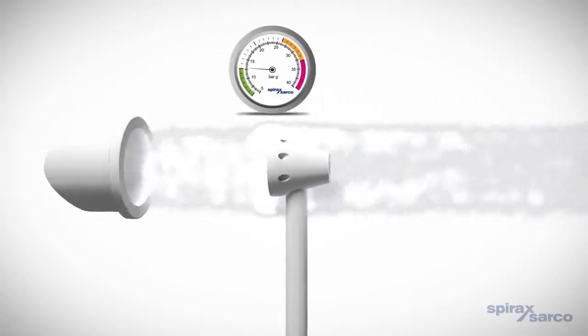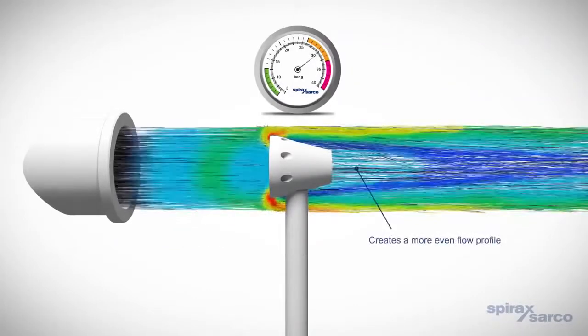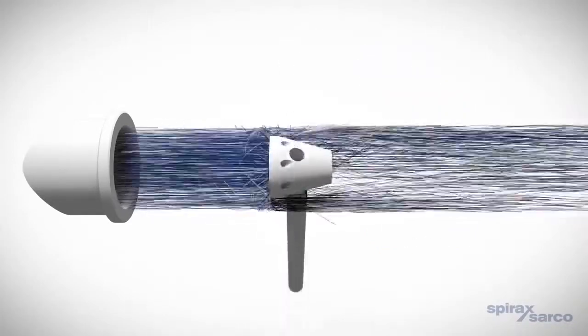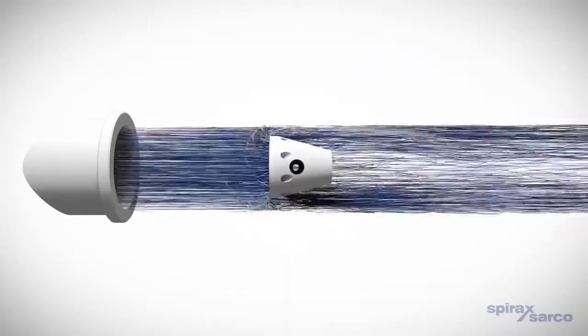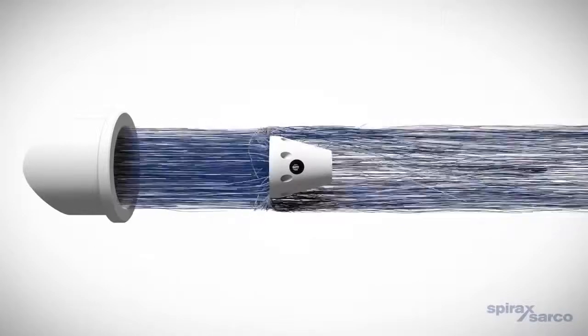The TFA's central fixed plate forces high velocity steam in the middle of the flow stream to mix with low velocity steam at the pipe walls. This creates a more even flow profile, which reduces the requirement for long straight piping upstream, allowing you to meter within small line sizes between DN25 and DN50 at steam velocity.